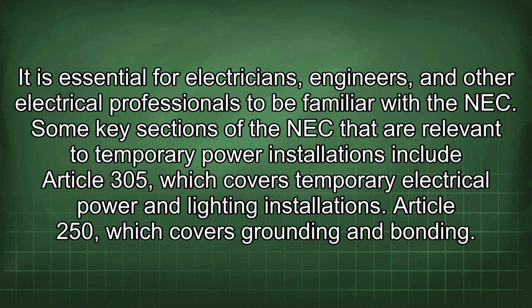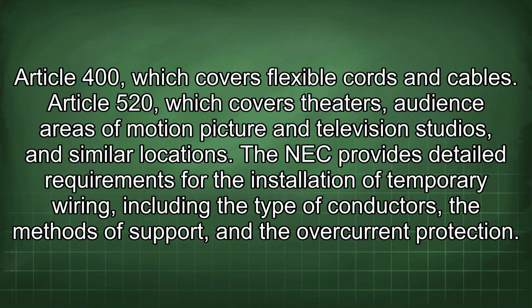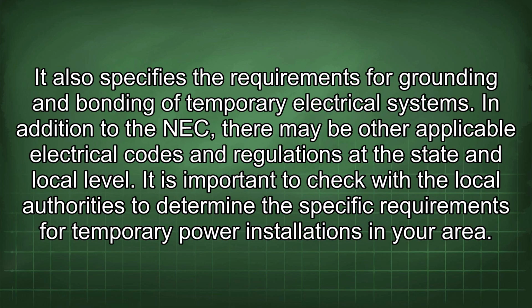Some key sections of the NEC that are relevant to temporary power installations include Article 305, which covers temporary electrical power and lighting installations. Article 250, which covers grounding and bonding. Article 400, which covers flexible cords and cables. Article 520, which covers theaters, audience areas of motion picture and television studios, and similar locations. The NEC provides detailed requirements for the installation of temporary wiring, including the type of conductors, the methods of support, and the overcurrent protection. It also specifies the requirements for grounding and bonding of temporary electrical systems.